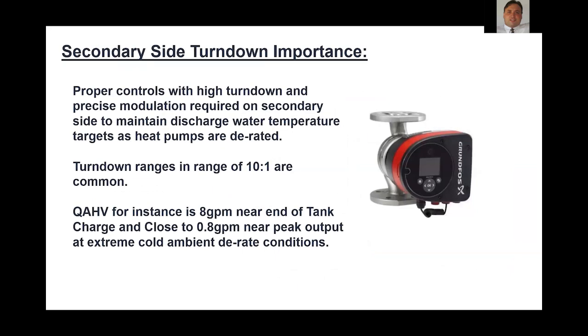Again, I kind of already alluded to this before, but that secondary side turn down is important with these systems. That ties into that critical brazed plate heat exchanger selection. And I talked about the high degree of turn down, and that's not uncommon with this equipment. So again, near the end of that tank charge cycle where you've almost recharged that tank up, with our equipment, for instance, you could see flow rates near 8 GPM right before the unit shut off.